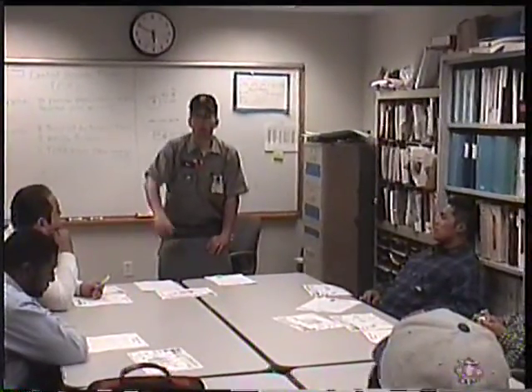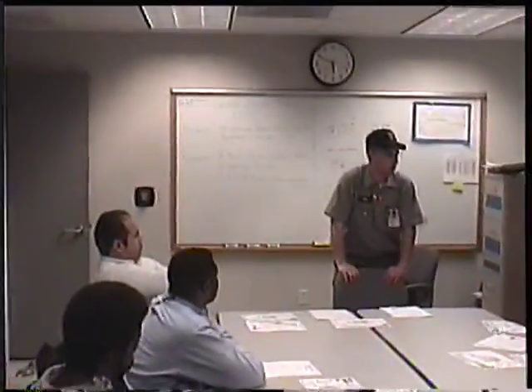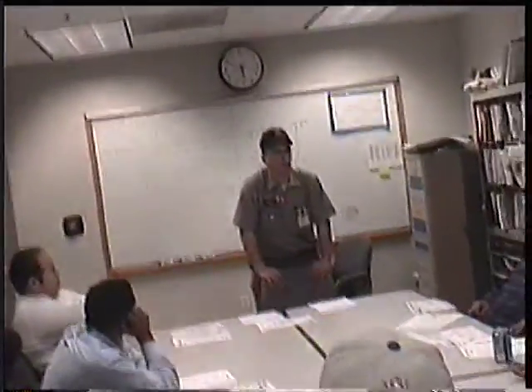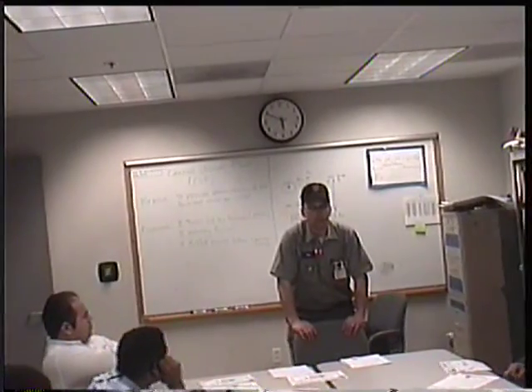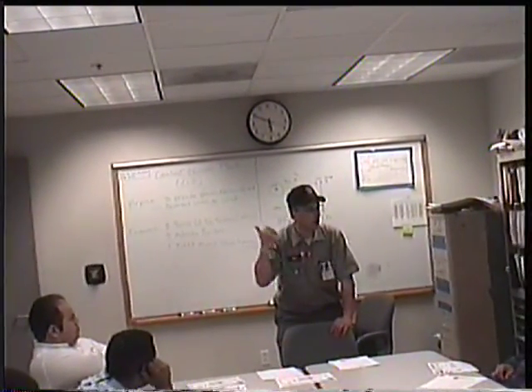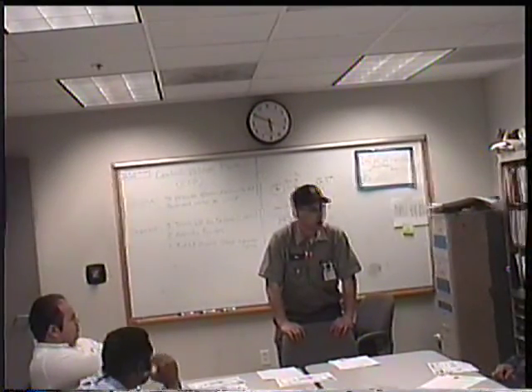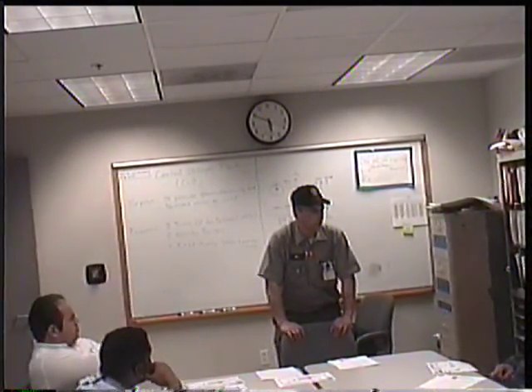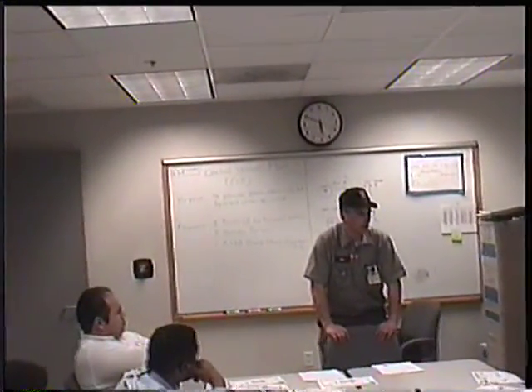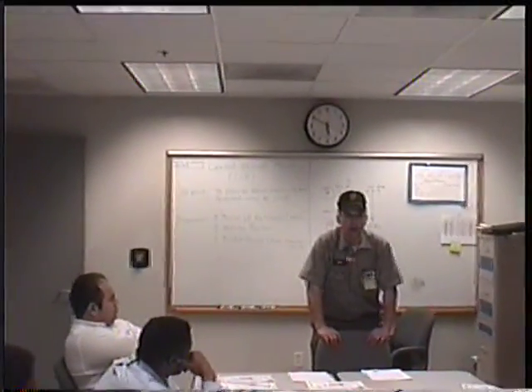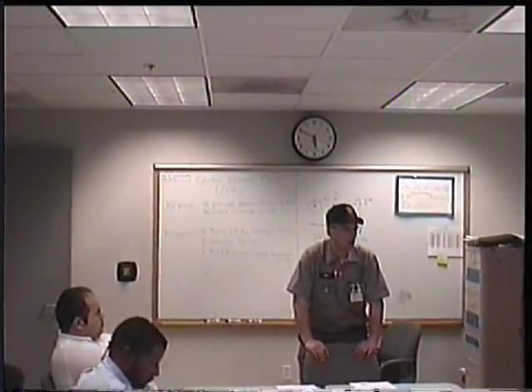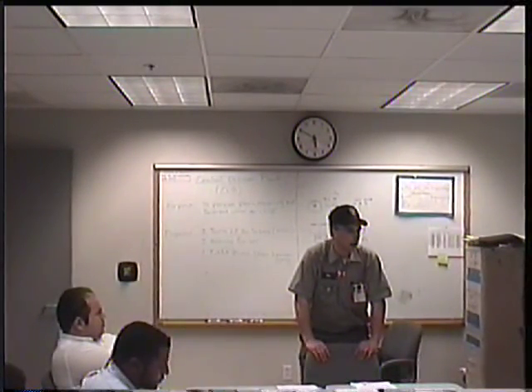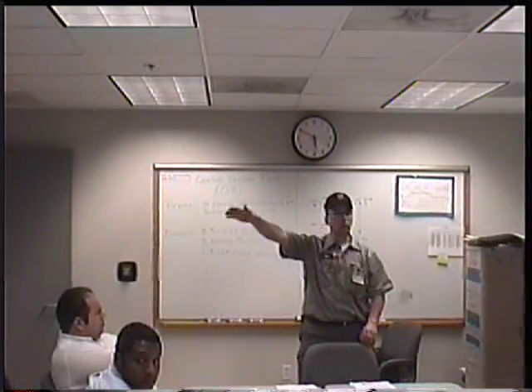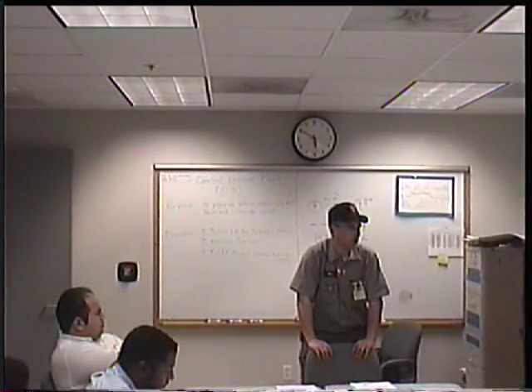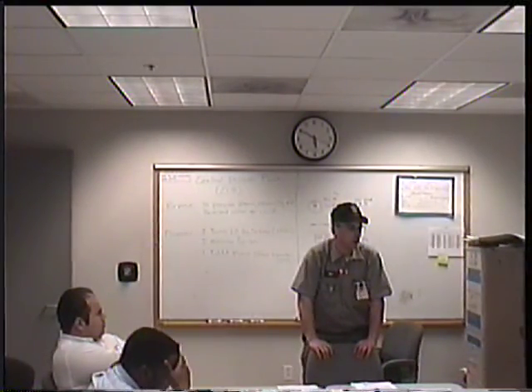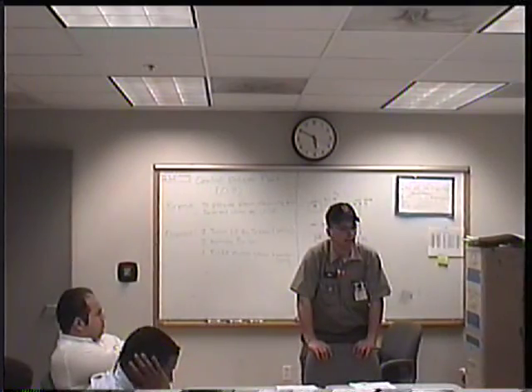Yeah, our stuff kicks on automatically, but we only have 3 emergency diesel generators next door, 3 big CAT units. This plant's capable of producing a maximum of 19 megawatts of power, and our backup generators can only produce about 9. So all they do is pick up essential services on campus, and you still have to restart everything. Like only emergency lighting will be going, and the hospital will get the majority of the power. So they get full lighting, right? Hospital, no, they're only on emergency power. We have 3 emergency diesel generators here, 6 megawatts, but we also have emergency diesel generators on campus. Each major building, for the most part, has their own. But again, those are only for things like elevators and emergency lighting.